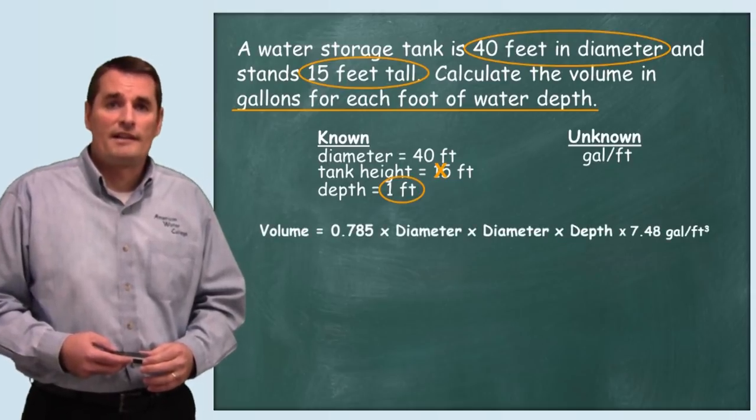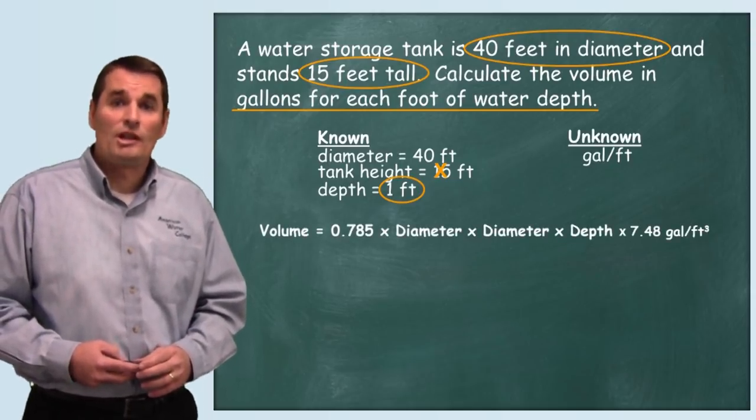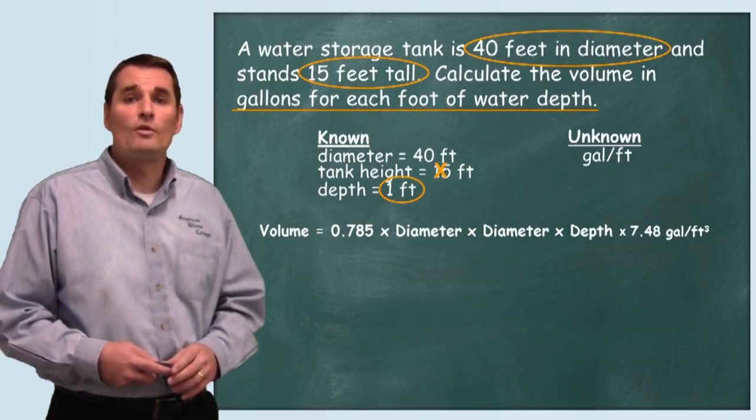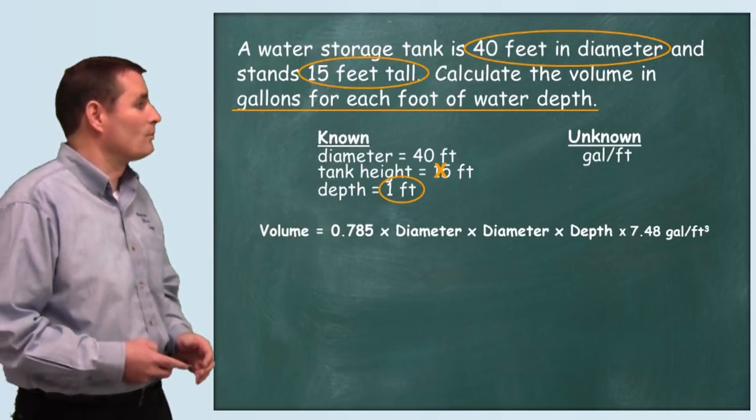The formula we're going to use for finding the volume is 0.785 times the diameter times the diameter times the depth times 7.48 gallons per cubic foot. You can see that written on the board.